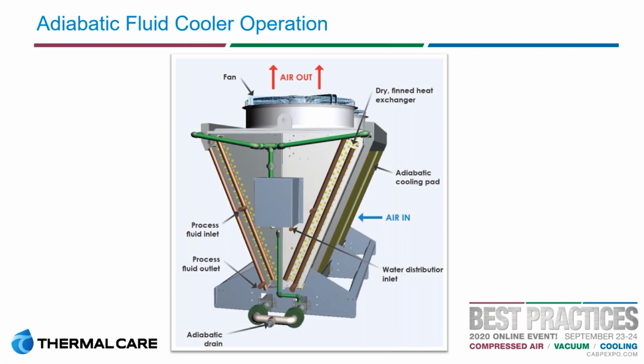So it lowers the actual temperature seen at the heat exchanger, which is exchanging the energy from the water into the air. Ultimately, those fans reject that now warm air out the top. One of the nice things about these units is that, one, you don't have to use evaporation all the time like a cooling tower does, because you're using forced air convection over a heat exchanger to get your cooling. Also, because you have that heat exchanger, it's a closed loop, so it's not open to the atmosphere like that cooling tower. So you greatly reduce the amount of chemical treatment you will need. The water stays clean, and you're not worried about dissolved solids because it's the same water over and over again. You're not exhausting that water supply and having to replenish it.